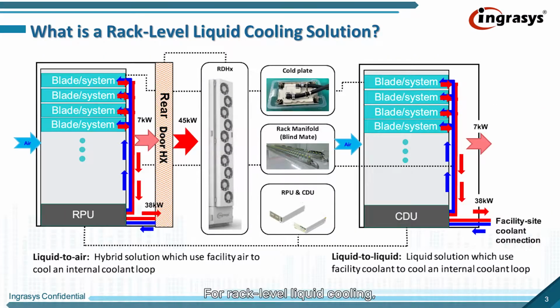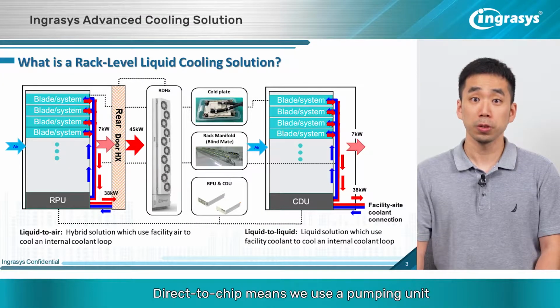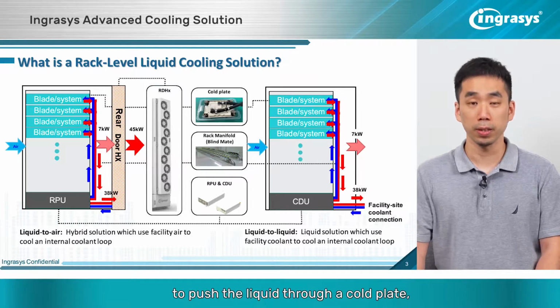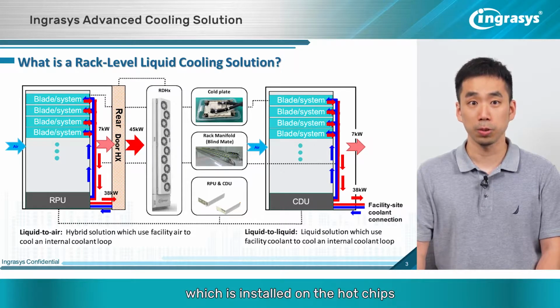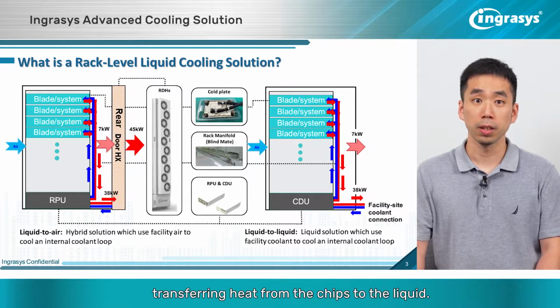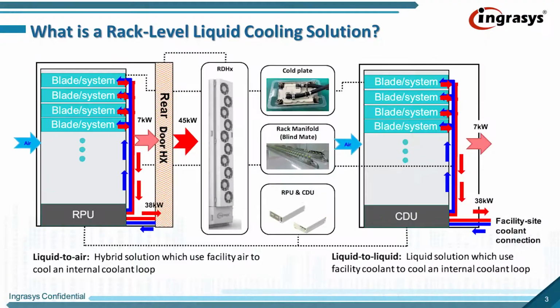For rack-level liquid cooling, we used a combination of direct-to-chip cooling and heat exchangers. Direct-to-chip means we use a pumping unit to push the liquid through a cold plate, which is installed on the hot chips like CPUs or GPUs, transferring the heat from the chip to the liquid. The heated liquid circulates to a rear door heat exchanger with fans or a plate heat exchanger that uses facility water to transfer the heat to the outside ambient.